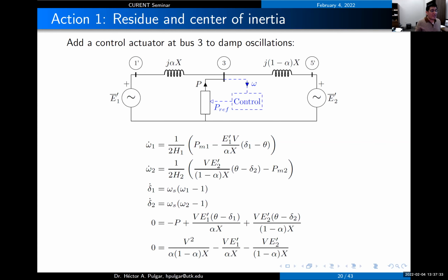So we have an idea now. Bus 3 can be located anywhere between bus 2 and 4, including a location that puts it at the center of inertia. The hypothesis is: if you put the control actuator at the center of inertia, because it has the highest concentration of inertia in the system, the controller will not perform as well as you want, since that point will not have much change in angle or frequency, and therefore your control logic will not provide much power to damp the oscillation.